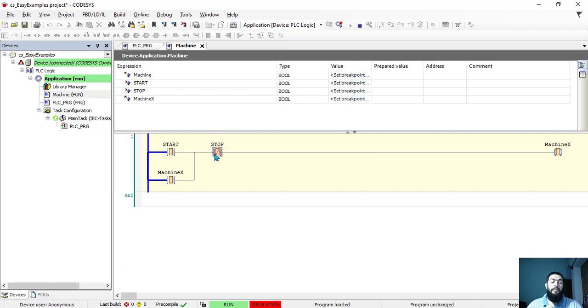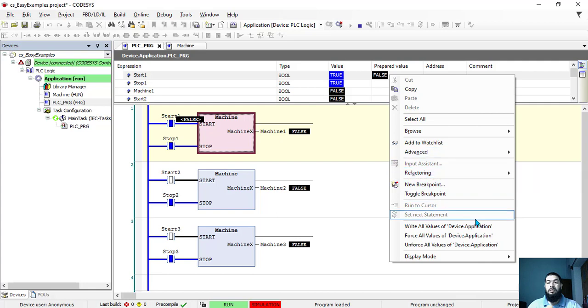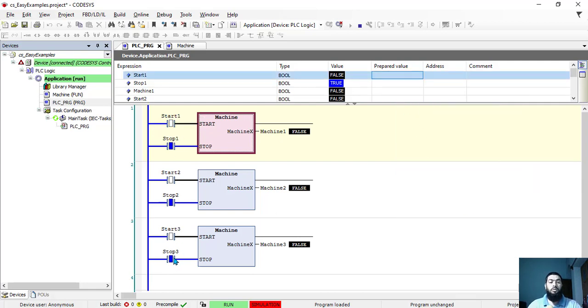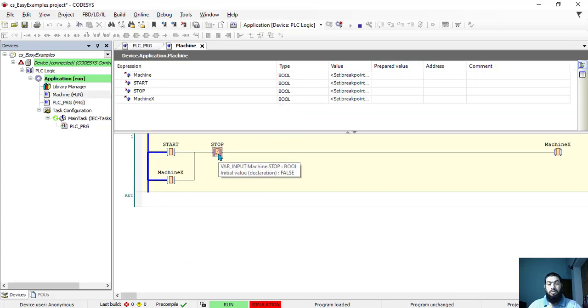This should be normally open, because for the stop button, if you use normally closed in the software logic, actually, let me show you another thing. Let's make it the default setting. So this is our default setting. All stop buttons are normally closed and all start buttons are normally open. But if you look inside, for the stop button we have used normally closed. So it's contradictory. Even though we have a normally closed signal, we use it reversely. We have to use normally open in the software logic, but physically it's normally closed. That's the difference.